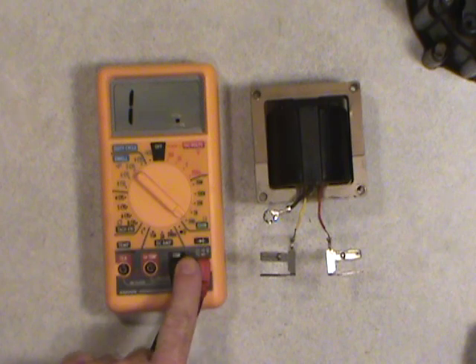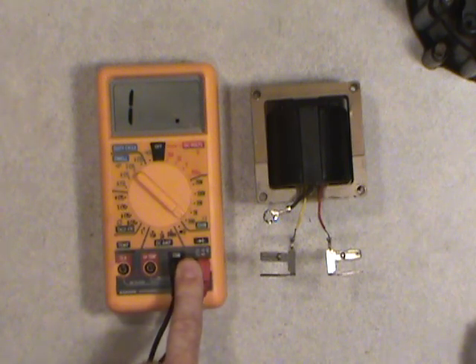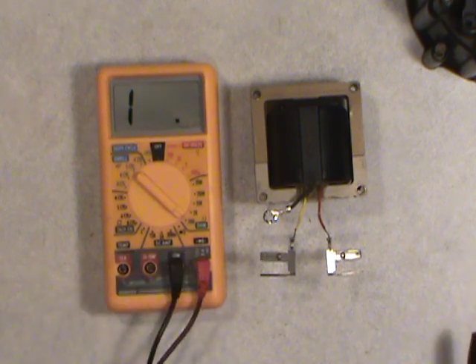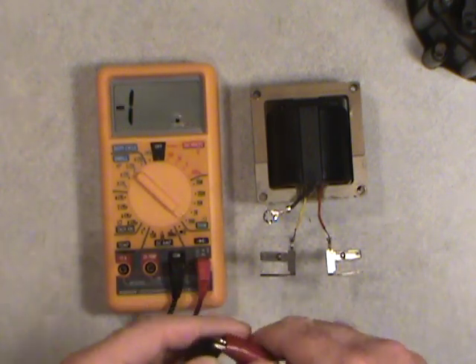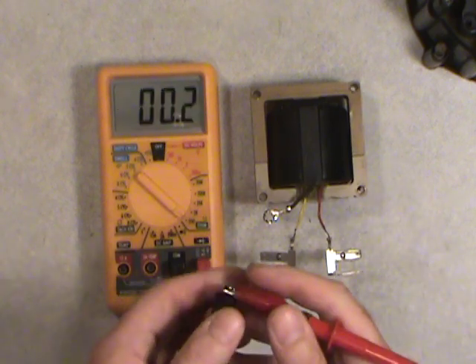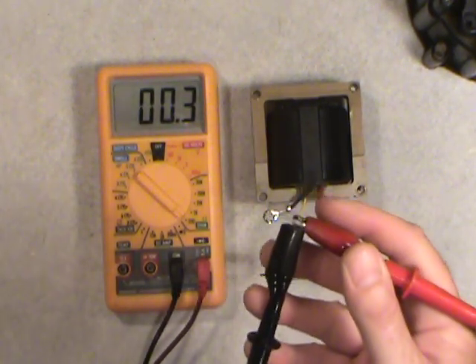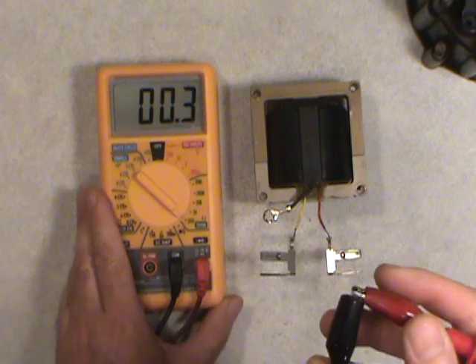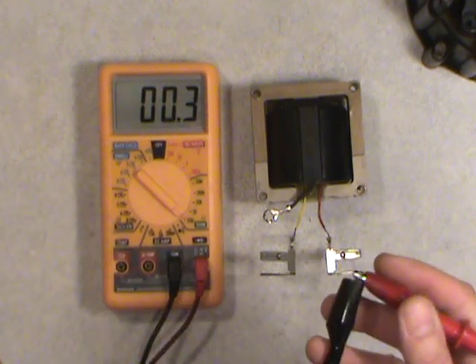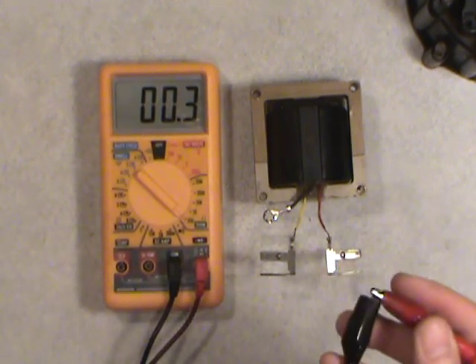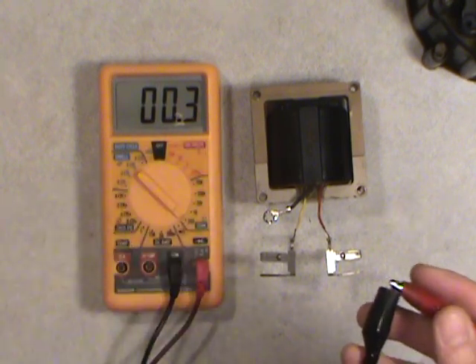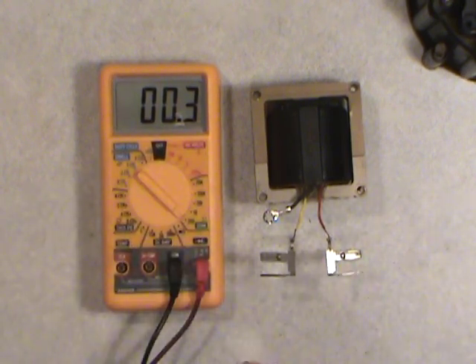I've actually got a probe and went between these two without the wires in, and it seems to be out 0.3 from the zero reading. So what we do is we basically connect the two leads together and see what we get. And this is how we calibrate this meter. Make sure that we can subtract that with some simple math and get a better reading, especially when it comes to the low ohm reading on this coil. So I'm showing 0.3, so we'll have to subtract that from our reading.